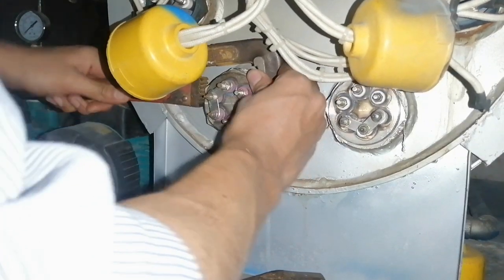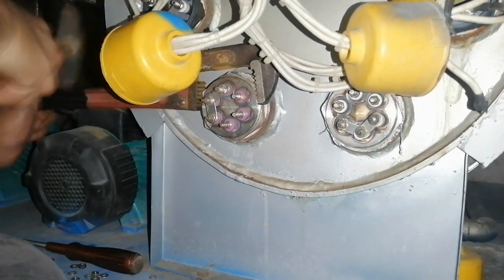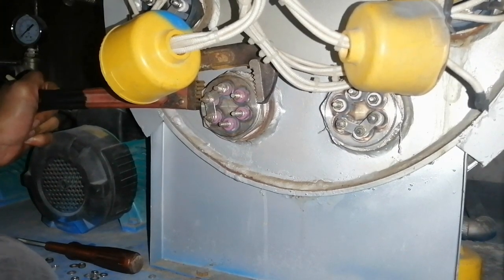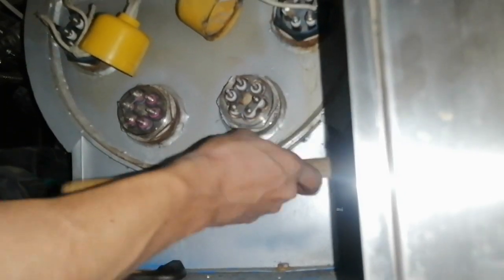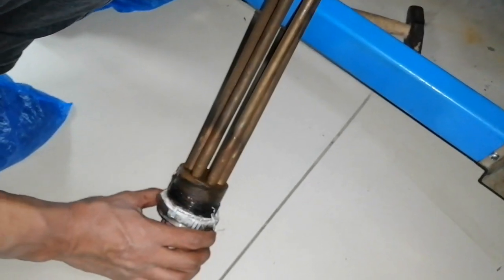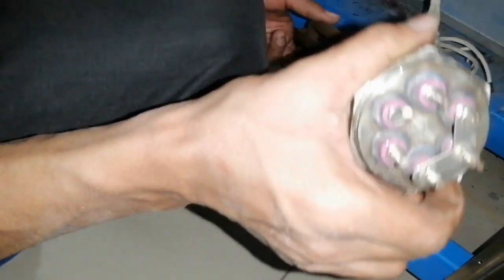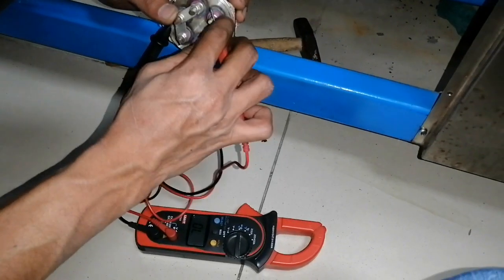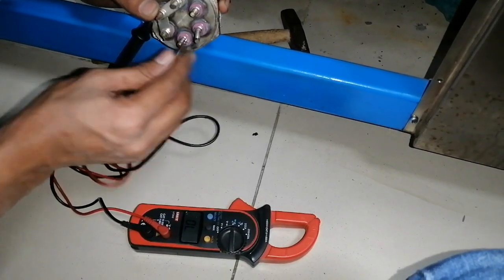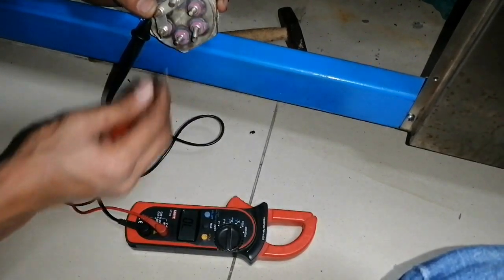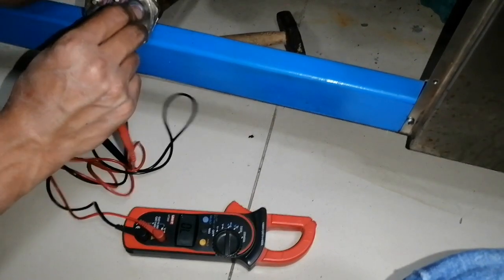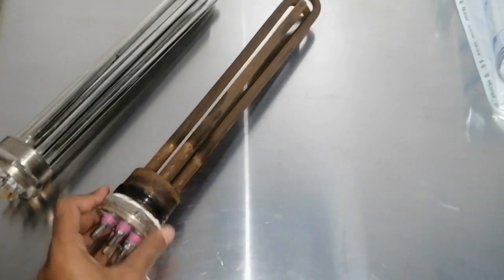I use this pipe wrench to open the faulty elements. So guys, here is the faulty element. I first check the element resistance, then we replace it, to confirm whether this element is faulty or not. From the multimeter, I'm checking the beep and the sound of the resistance. So two sides are open and one side is closed. So here is the faulty element which needs to be replaced.